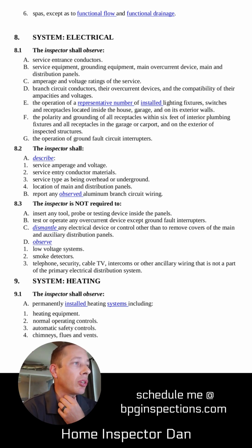Describe the 1. Service amperage and voltage. 2. Service entry conductor materials. 3. Service type as being overhead or underground. 4. Location of main and distribution panels. B. The report should report any observed aluminum branch circuit wiring.